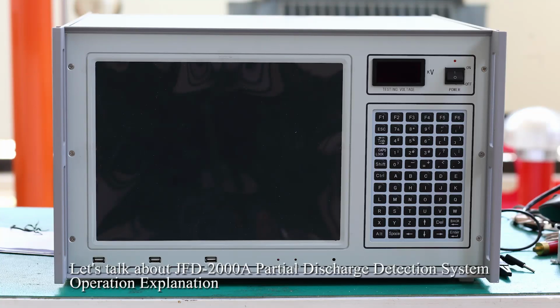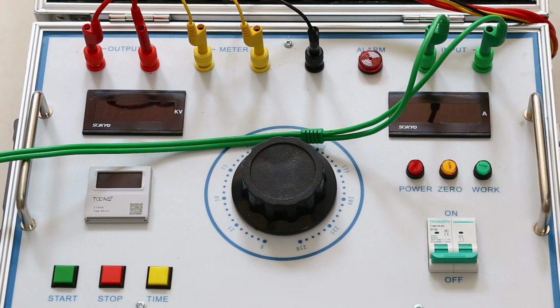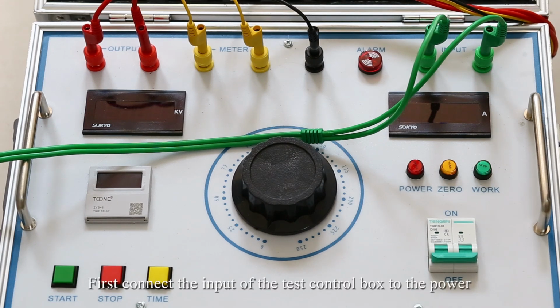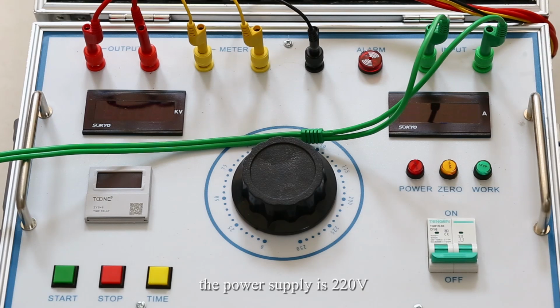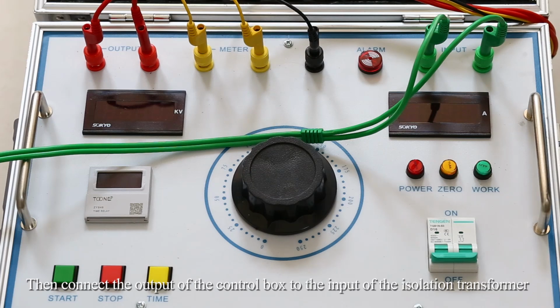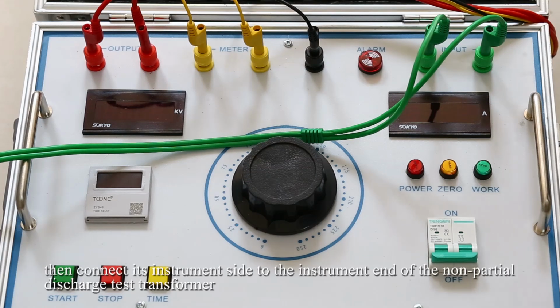Let's talk about JFD-2000A partial discharge detection system operation. First, connect the input of the test control box to the power supply. The power supply is 220 volt. Then connect the output of the control box to the input of the isolation transformer. Then connect the instrument side to the instrument end of the non-partial discharge test transformer.